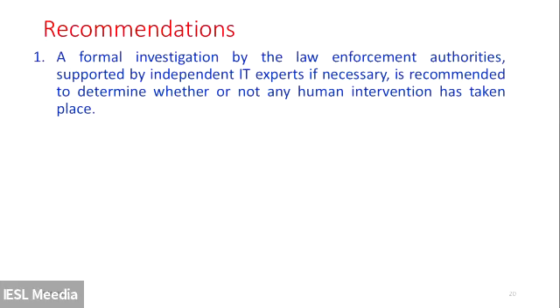The first one is somewhat of a very strict kind of recommendation. Why we went for that is, in this particular incident, non-persisting earth faults are typical in a power system. That's fine. And then, plus there's an end-fault protection operation. That is also fine as far as you know the reason, but in this case, there were technical problems associated with this.